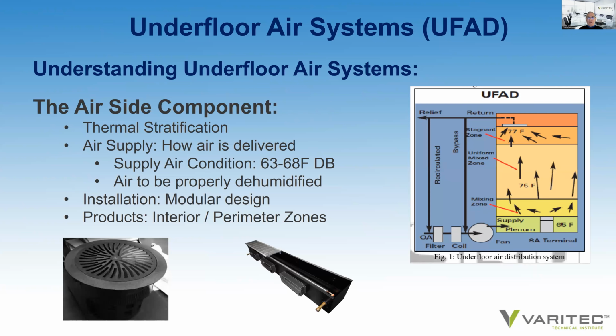So the air side component, how is air delivered to a space to create a semi or fully thermally stratified environment? Air is supplied through each diffuser in the floor or in perimeter zones that would provide cooling and heating linear troughs. And air is supplied at 63 to 68 degrees to prevent overcooling of ankles and feet. I remember my mentor in the industry, Jerry Sipes, who was VP of Price Industries at the time, told me that he actually achieved his PhD in mechanical engineering studying thermal comfort at Kansas State University. And they actually determined that providing the temperature differential from the foot to the head remains within 5 degrees, an occupant cannot discern the temperature differential.